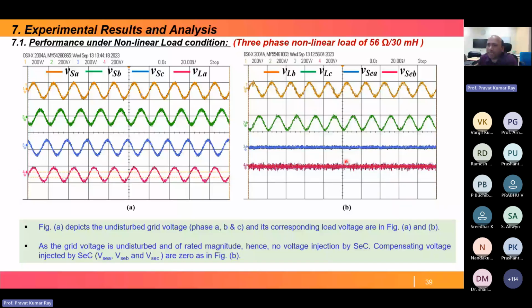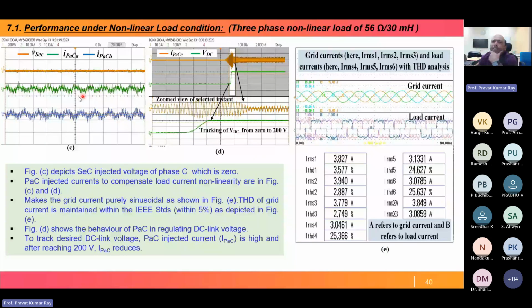But in this case, what happened? The load is nonlinear, so the compensating signal needs to be properly visible. These are the compensating signals: parallel converter signal IPAC, parallel converter A, parallel converter B, and parallel converter C. So when the load is nonlinear, these are the injecting signals, so that the grid current becomes sinusoidal.